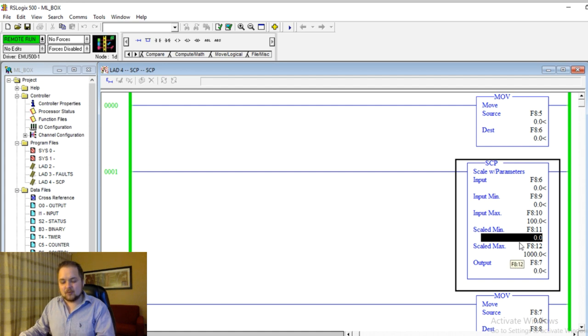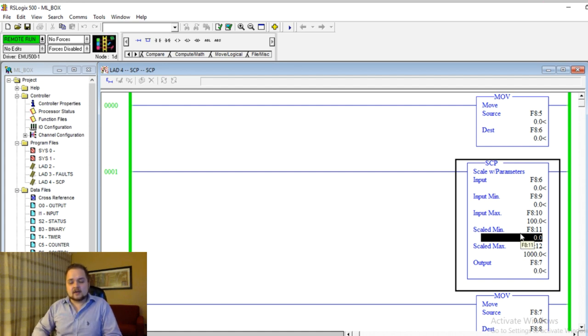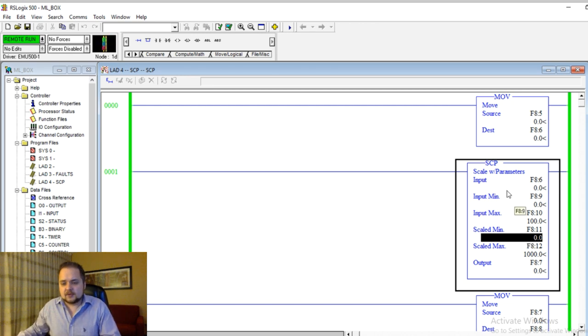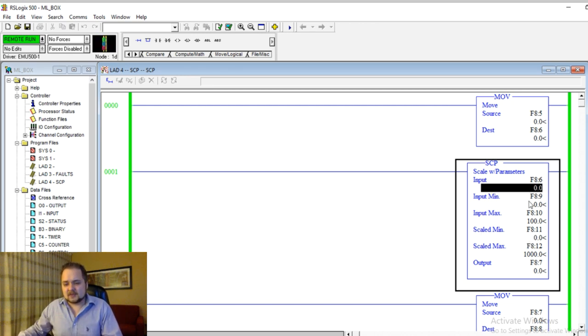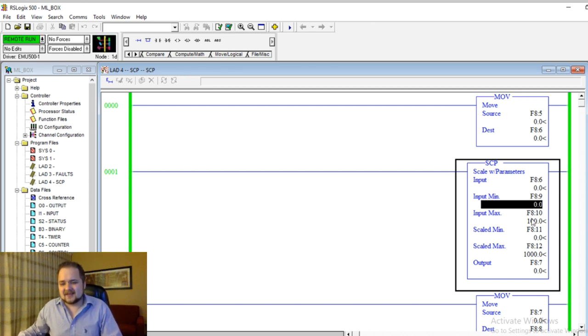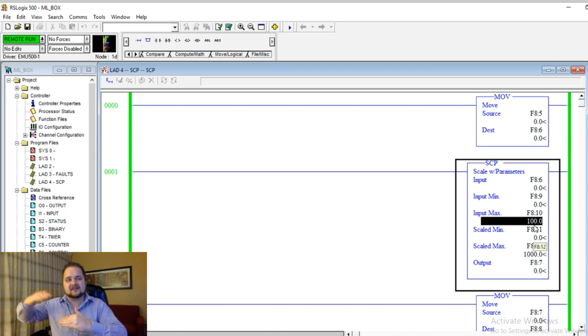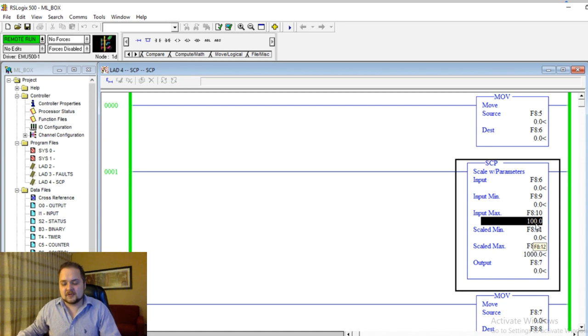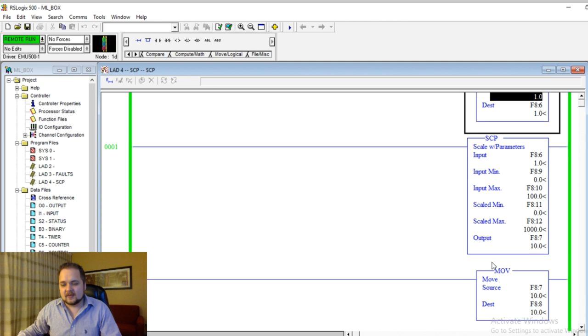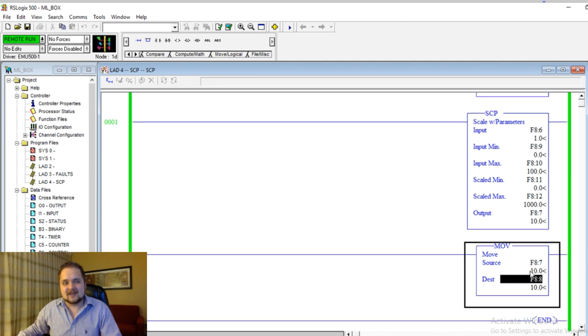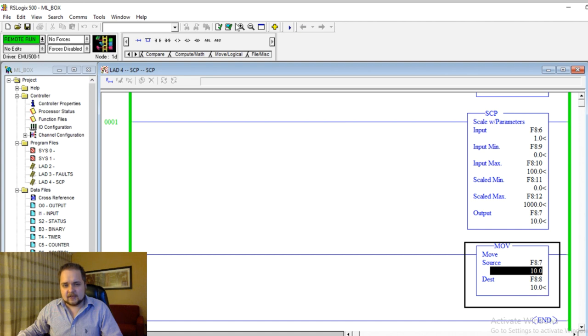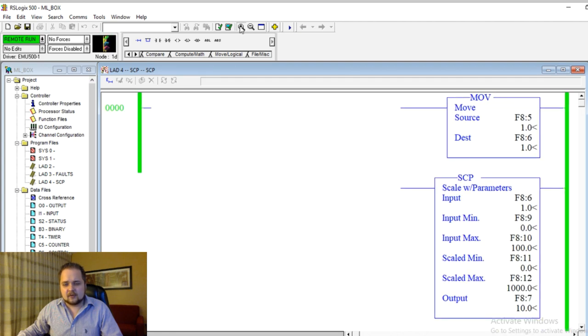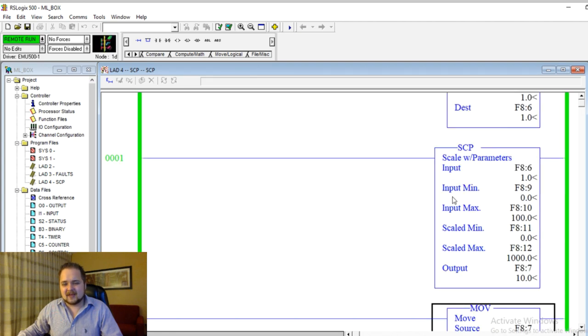So scaled min is a zero. So what's happening here is essentially that we're taking this input, and since it's a factor of 10, as you can see, it's zero to 100, the zero to 100 becomes scaled to zero to 1000. So what that means in practical terms is if the input is one, then that scales our output to a value of 10. And that's all there really is to it in terms of simple math.